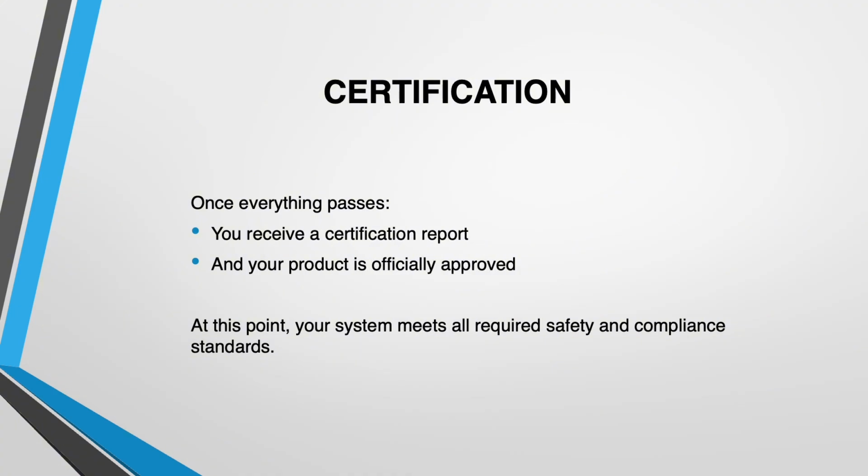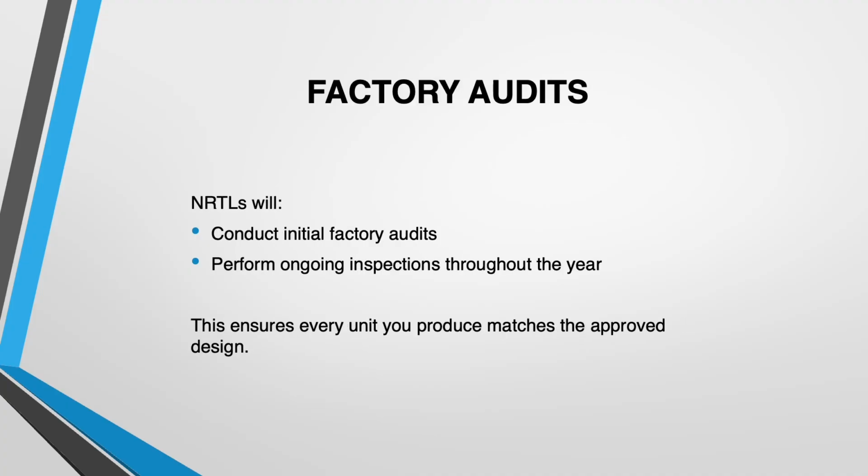At this point, your system meets all required safety and compliance standards. But the process doesn't stop there. NRTLs will conduct initial factory audits and perform ongoing inspections throughout the year. This ensures every unit you produce matches the approved design.